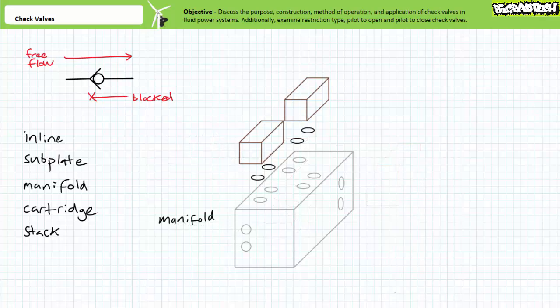Manifolds, if you think about it, are kind of like large subplates to which a number of valves can be externally attached. The manifold is a machined metal block into which internal passages are drilled. The manifold is in effect a common circuit free of potential leaks associated with external plumbing.